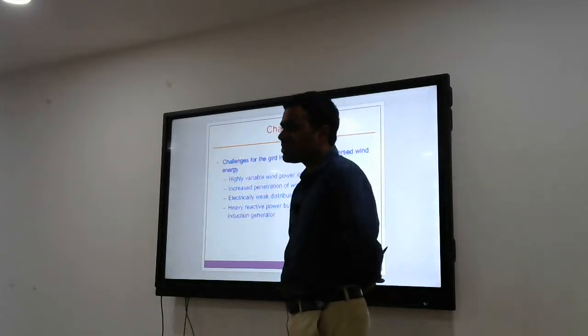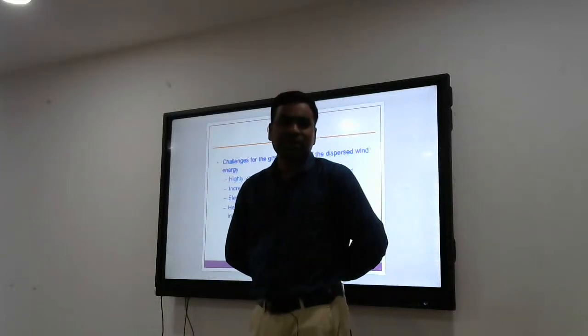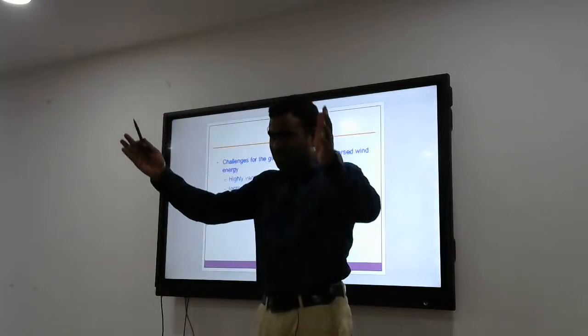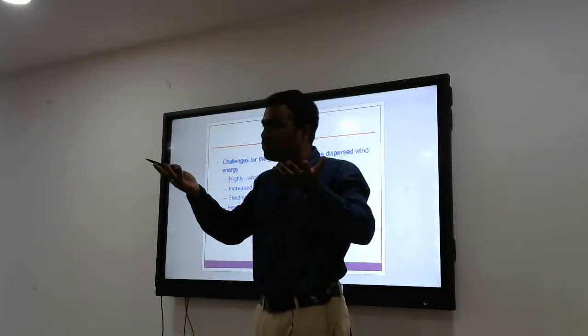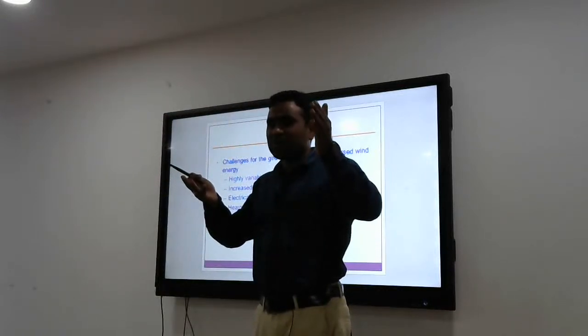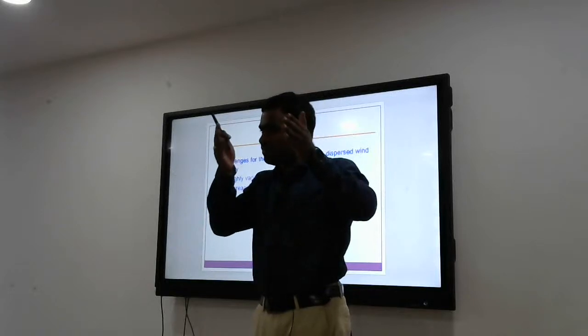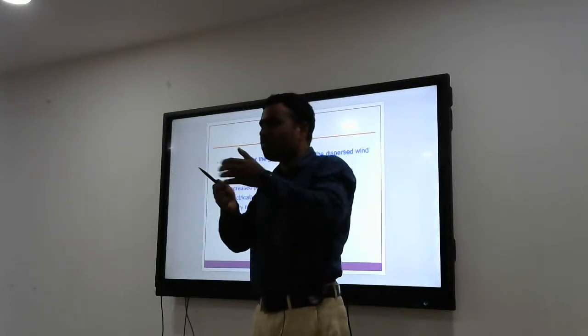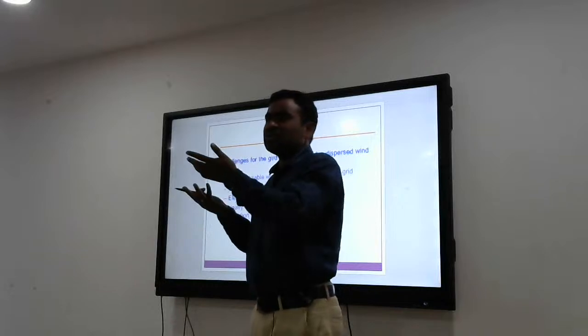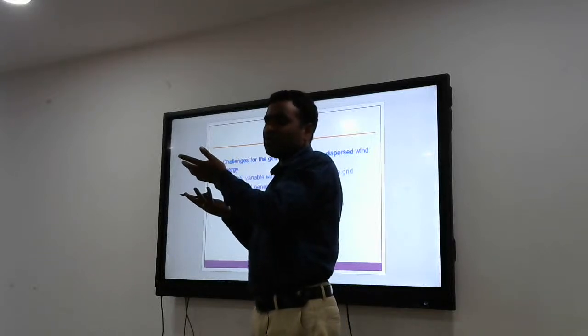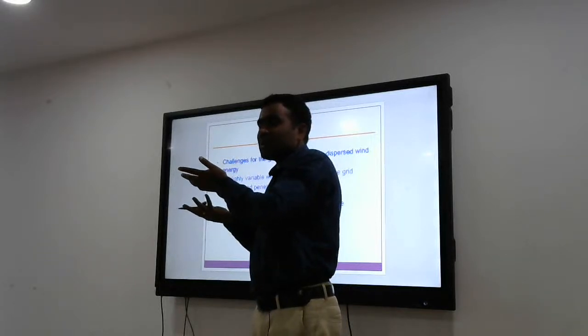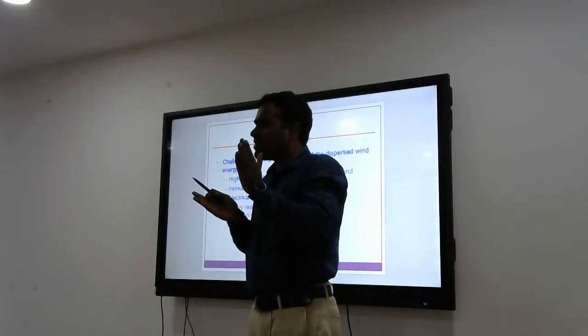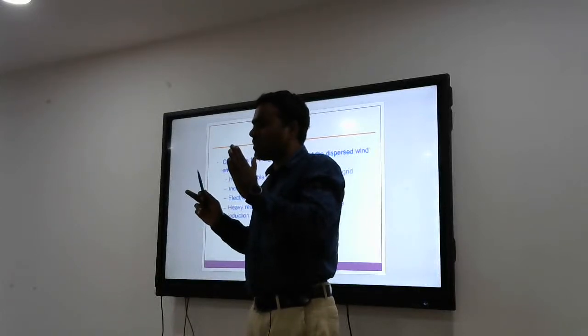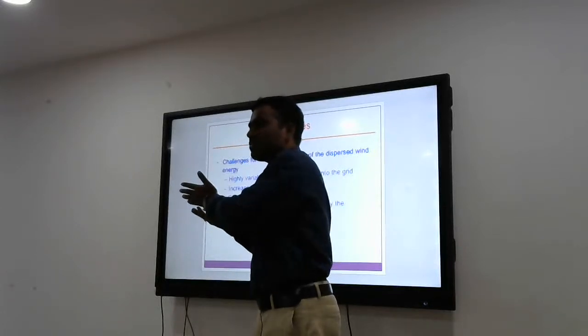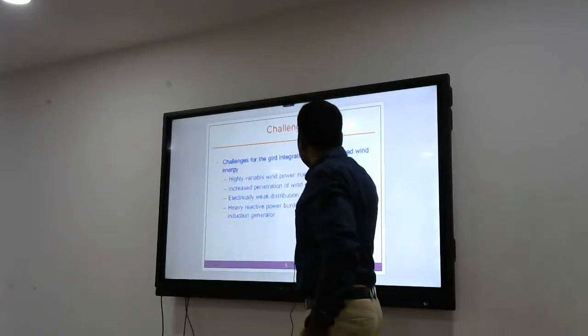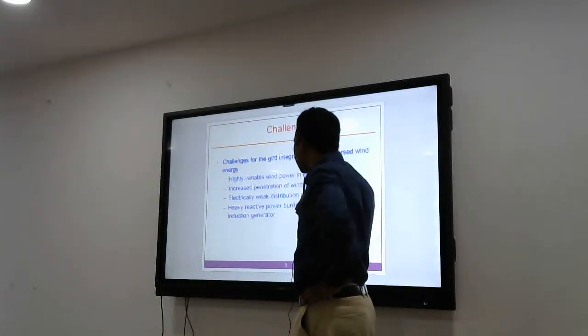So you need some mechanism to convert variable voltage, variable frequency into constant voltage, constant frequency. That's where our power electronics comes in. Otherwise, there may be two converters to convert this variable voltage, variable frequency into DC. And once you get DC power, you can generate whatever voltage and frequency you want directly, because that is an inverter. If you have DC, you can generate AC voltage and frequency, whatever you want, and connect to the grid. So that is actually the challenge here.